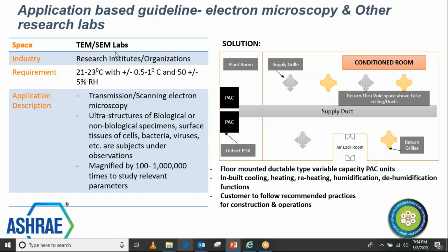And there are other applications like TEM, SEM labs where different testing is done, and these testings are also very important. Again, the tolerance is very low here, 0.5 to 1, and mostly they ask for 0.5 to 0.8. So this is also very important here. In all these applications the electronics load is not so high, but they demand close temperature and humidity control, and many of them demand 24-hour operation. So a comfort air conditioner cannot meet these kinds of requirements. So precision AC is the only choice for these kinds of applications.